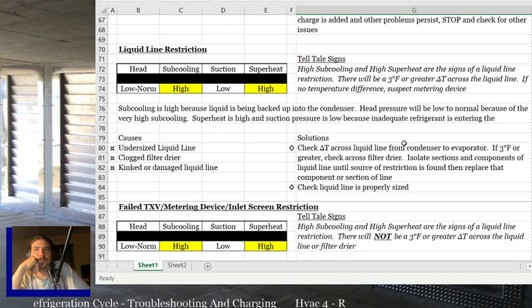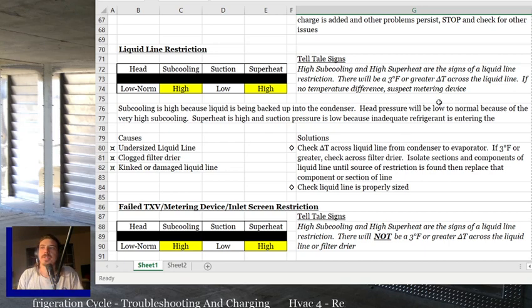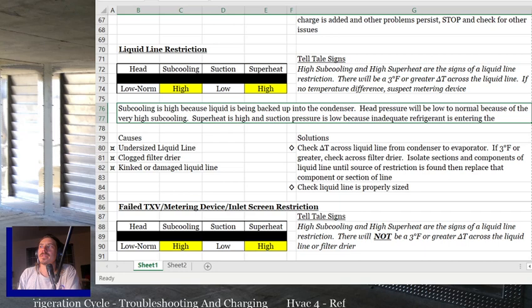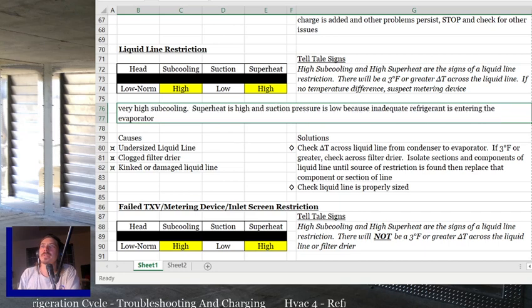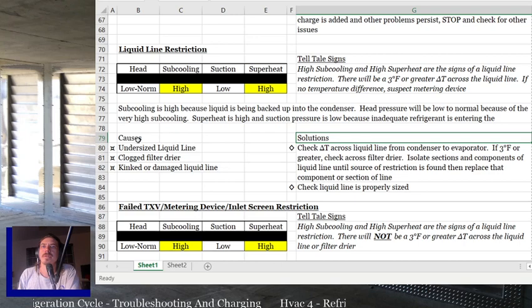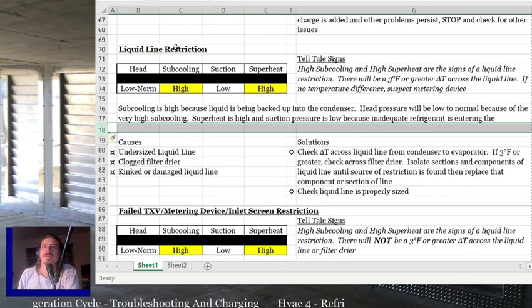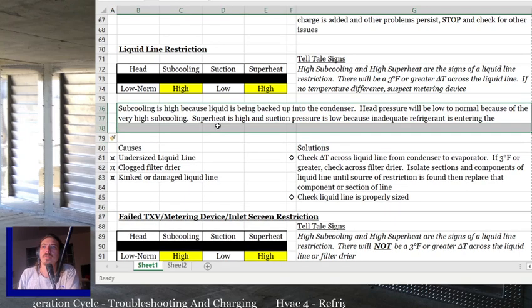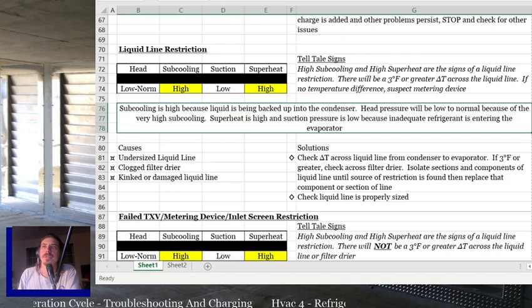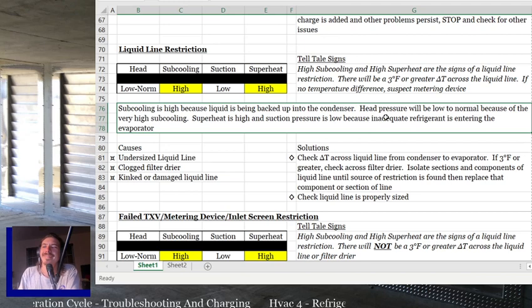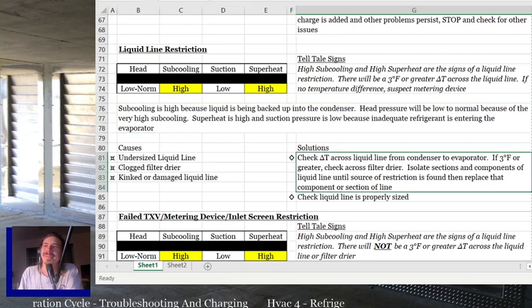The superheat is high and the suction pressure is low because inadequate refrigerant is entering the metering device. Or entering the evaporator. So I actually don't have enough space for that. Need to fix that. Another good thing about going through this together, I can fix the issues before you tell me I got a bunch of problems when I make it a PDF.